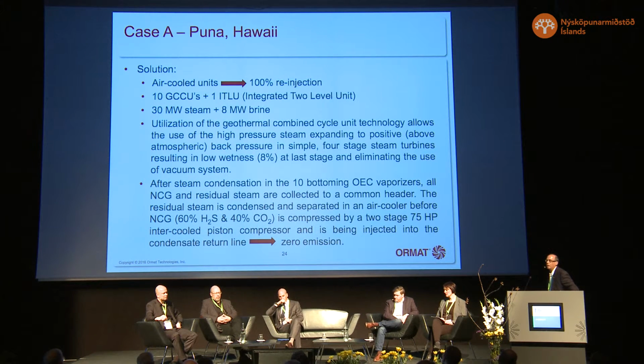What we did is that we took the 19-bar steam and entered it into a 4-stage steam turbine. The exhaust pressure is 2 bars. The wetness in the last stage was 8%. After the steam flows out of the steam turbine, it condenses in 10 bottoming cycles. The NCG, with some residual steam that still exists with the NCG, are collected to a common header. Then we have an air cooler to condense as much as possible of the steam.